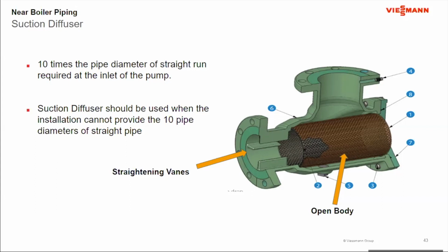Most of our mechanical rooms are starting to get smaller and smaller, and there may not be the space for this 10 times the diameter. So the suction diffuser goes into the location where it can't be met. So water flow comes in here. It has an open body, and after it comes in the open body, as it approaches the pump, it goes through these straightening vanes. So the straightening vanes help clear up the turbulence in the water to get it to a more laminar flow as it enters into the pump in those applications where that 10 pipe diameters can't be used. So from a standpoint of the mechanical room, when I find a pump, in most cases, I expect to see that suction diffuser on the inlet side.